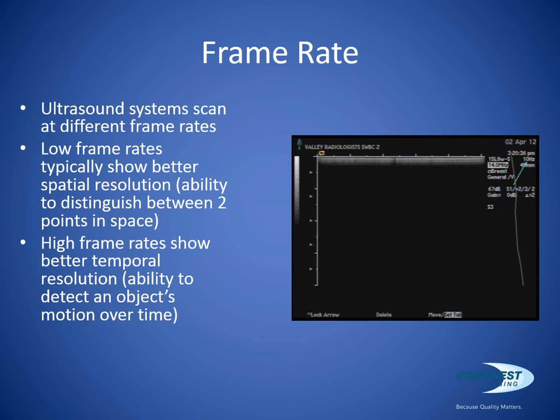Space-time or resolution. Systems allow you to somewhat adjust your frame rate by a button. On the Acuson Sequoia, it's called space-time. On some other systems, it's called resolution. It allows you to adjust the processing power of the ultrasound system to optimize either spatial or temporal resolution.